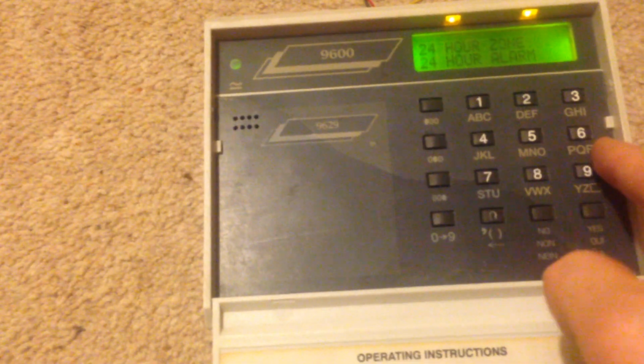We could have a technical alarm, which just sounds the keypad sounders because it shows the zone has been violated in a place where no one should go. It doesn't need to be a 24-hour alarm, because if an employee went into the refrigerator, for example, you'd have a police knock on your door within 5 minutes, and that wouldn't be a very good idea. So we press no, and then it's a 24-hour alarm, so if the safe is open, for example, the alarm would go off without the master code owner, the manager, omitting that zone prior. So then we go back to audible PA.